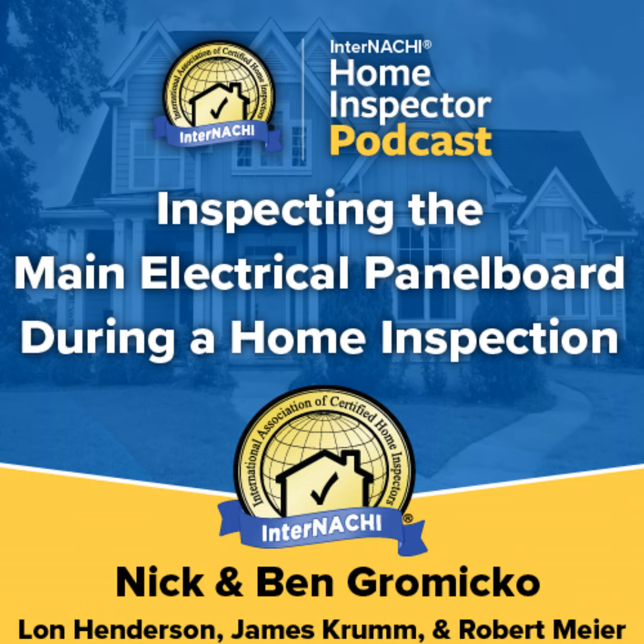The grounding electrode conductor, or GEC, and the grounded service conductor are bonded together to the metal service enclosure by the main bonding jumper, a screw or jumper connecting the neutral bus bar to the cabinet enclosure. The equipment grounding conductors, the grounding wires, are also brought to this point and tied to the grounded service conductor, the neutral conductor, and to the grounding electrode conductor, or GEC. The other end of the GEC is connected to one or more grounding electrodes, such as an underground water pipe and grounding rod.